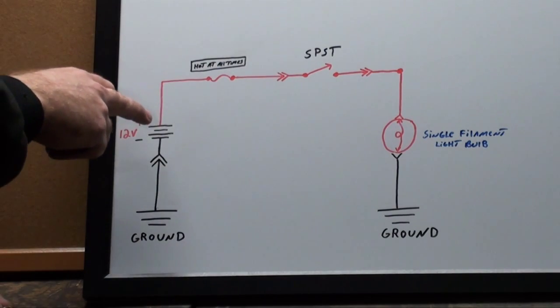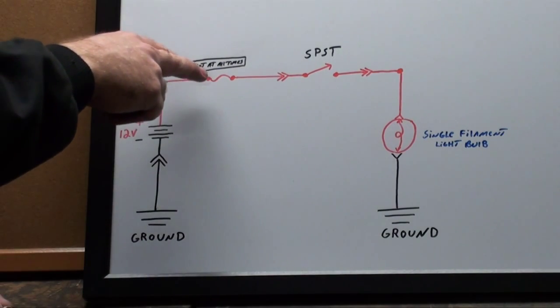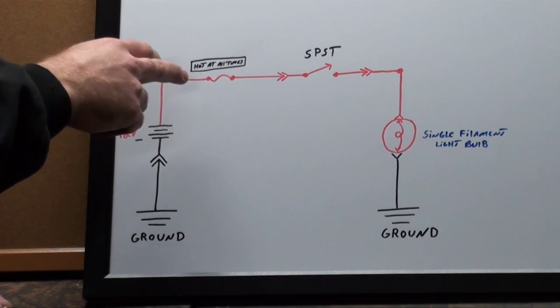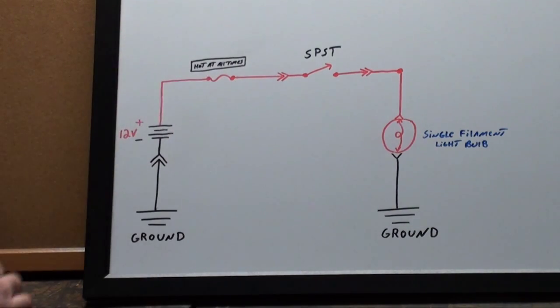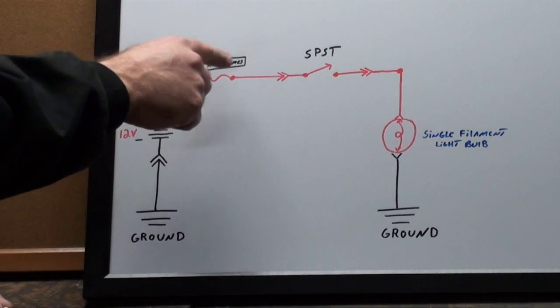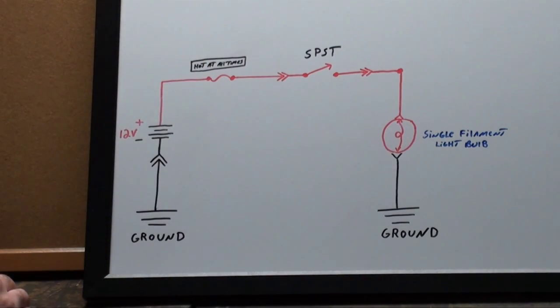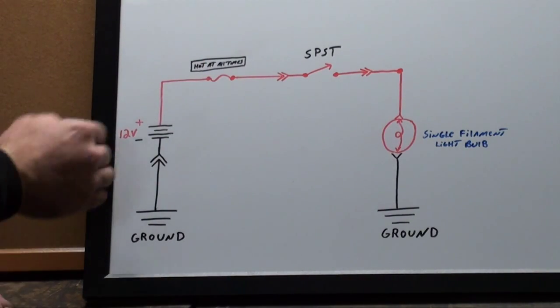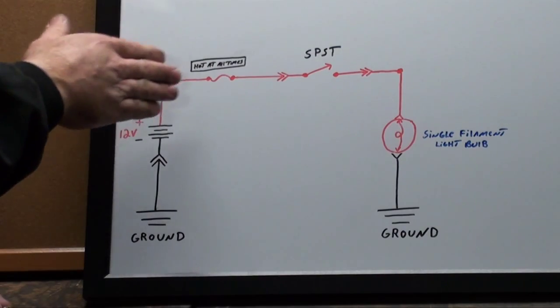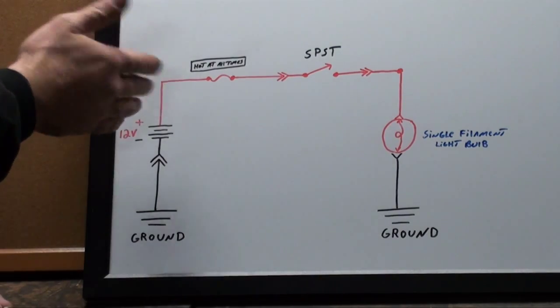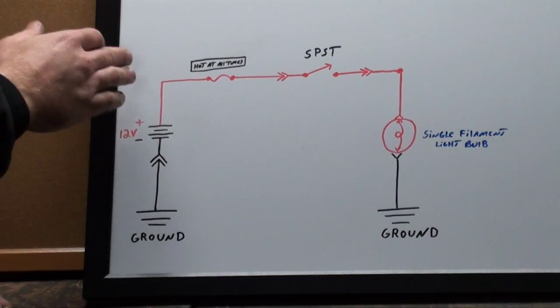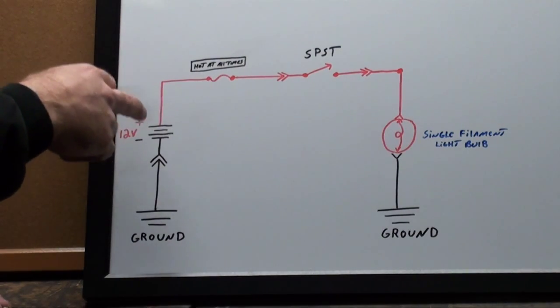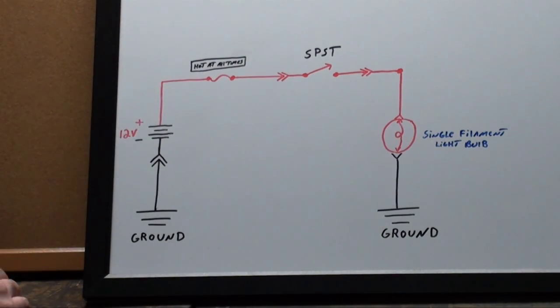So on the positive side, I come up. First thing in line here is the fuse. As you can see, the voltage indicator box says hot at all times, because there's nothing between the battery and that fuse. If there was a switch there, it would be a different circumstance. However, there's nothing between the fuse and the battery, so that's going to be hot at all times.